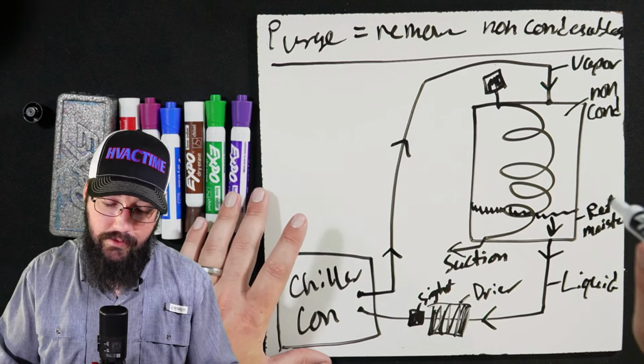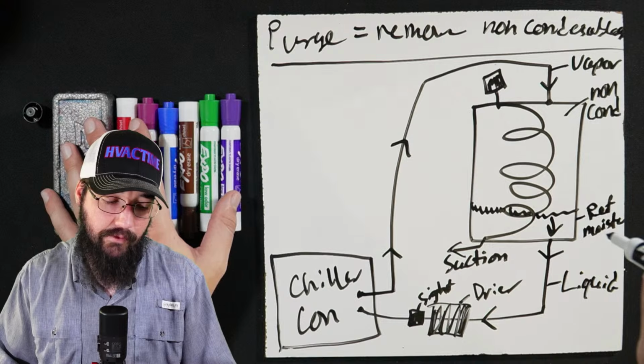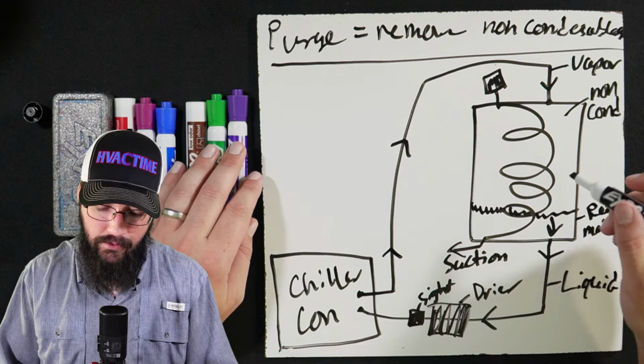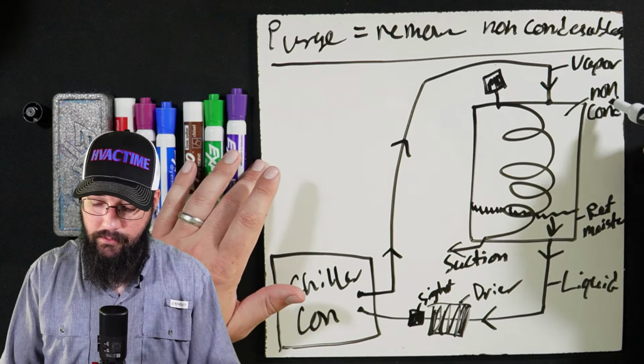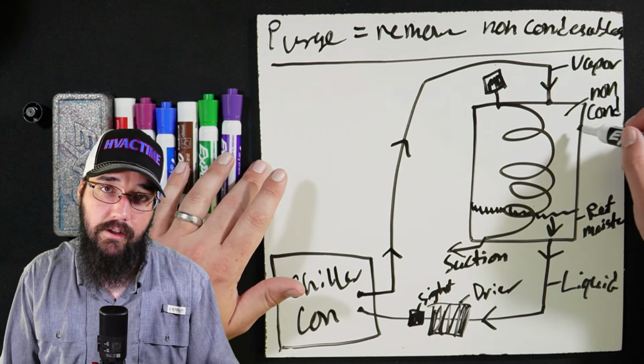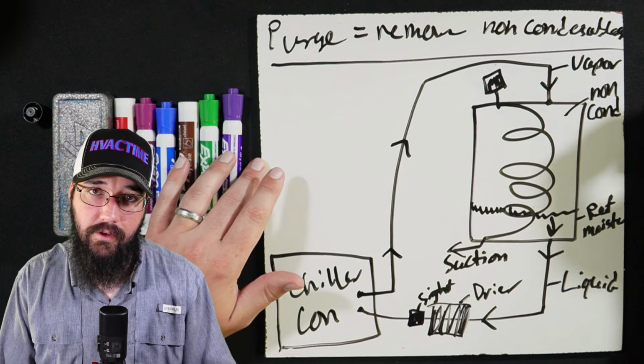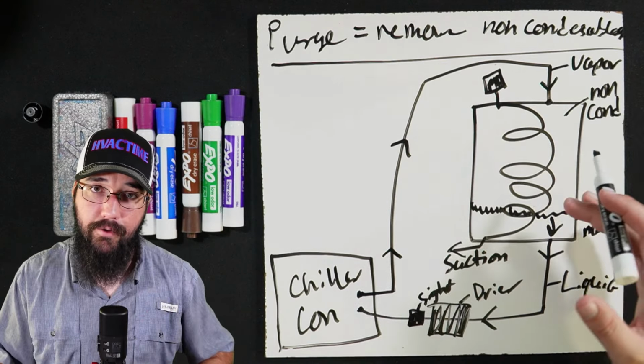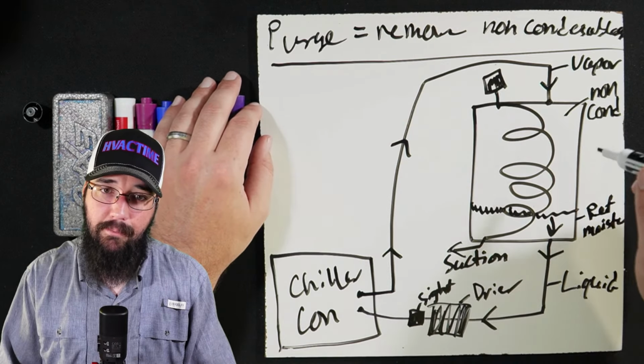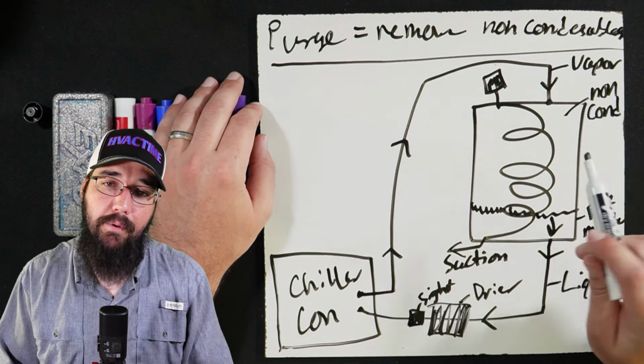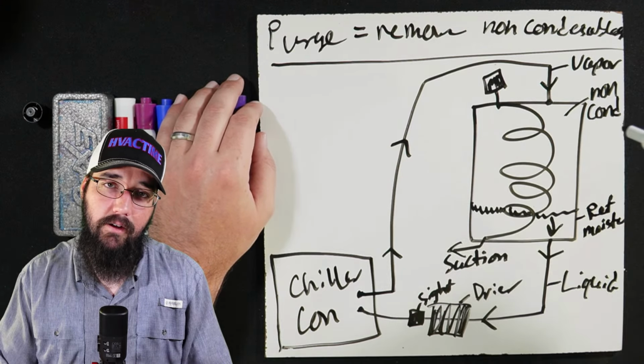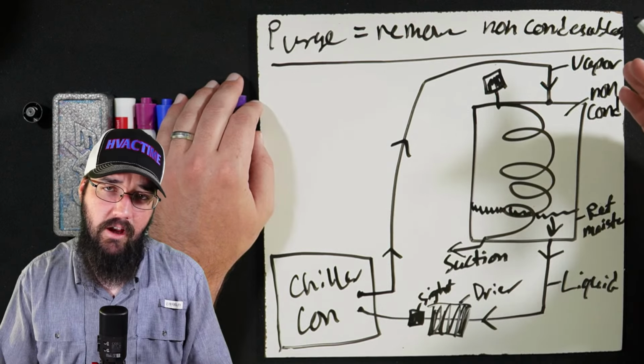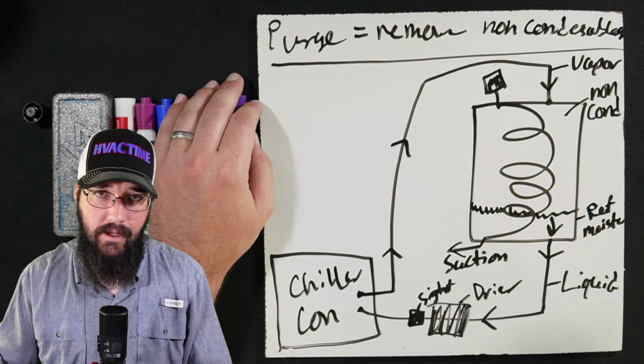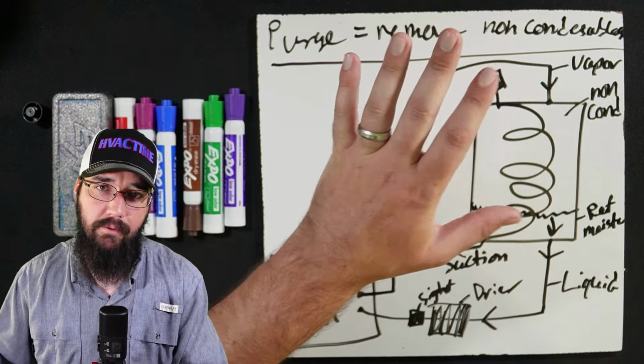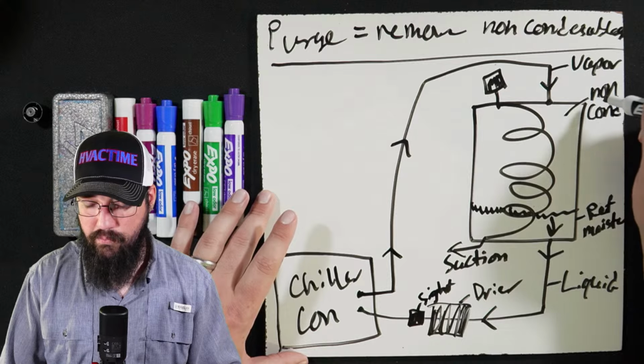Now, on the York side of this is where they get slightly different in how they implement what's called the pump out. So a pump out is when we sense that, okay, there's a lot of non-condensables up here, and it is time to remove those non-condensables. So we have a separate little special pump that sits up on the purge unit's frame, and we activate that pump. We open some solenoid valves, and that pump sucks those non-condensables off the top of our chamber and rejects them outside, or it just gets them out of our system and puts them back where they don't matter. So that is called the pump out.